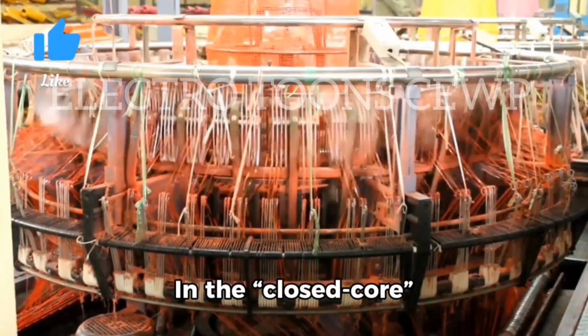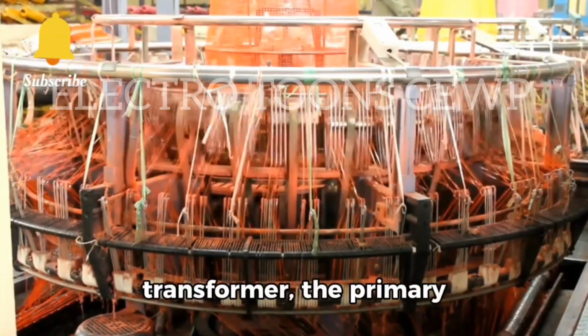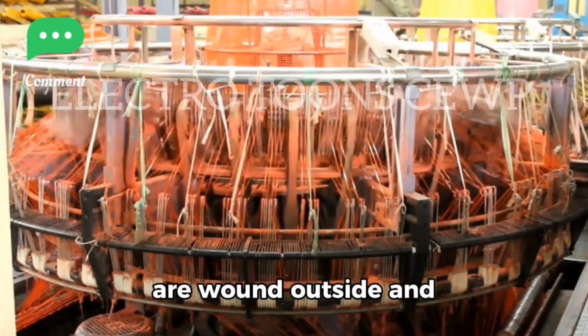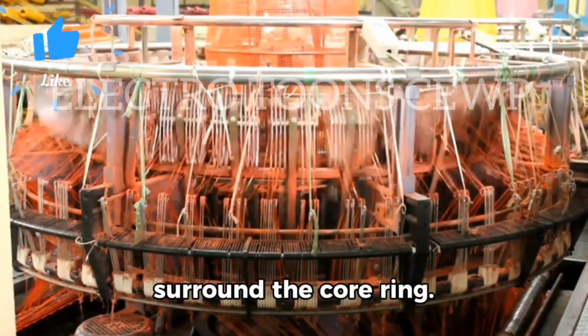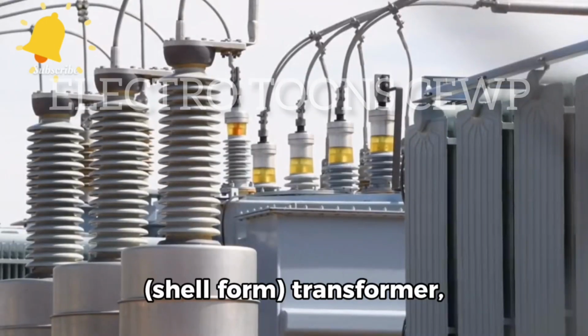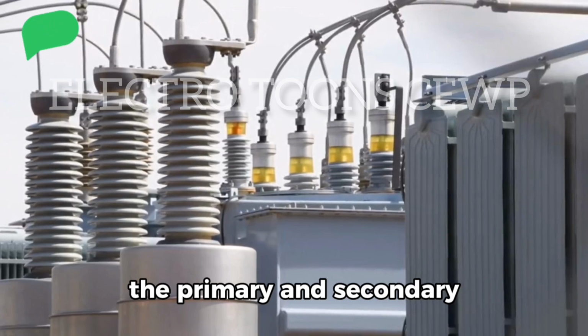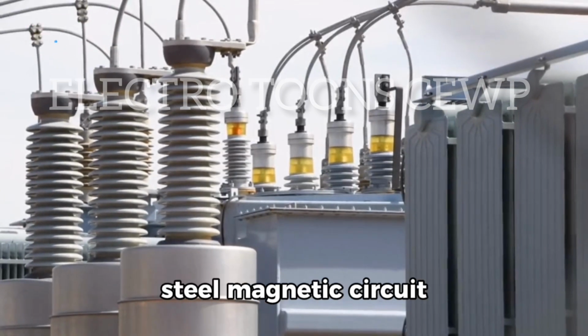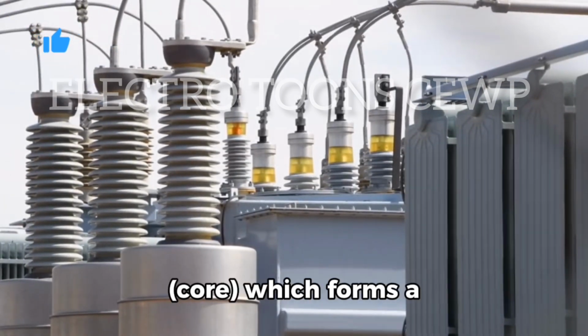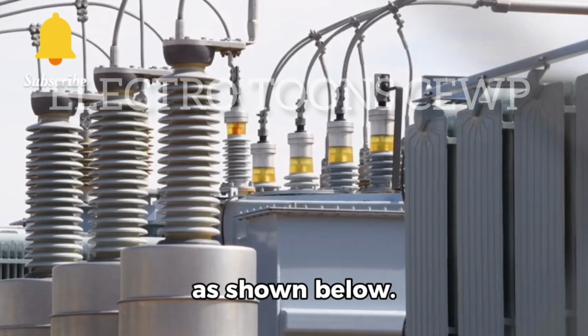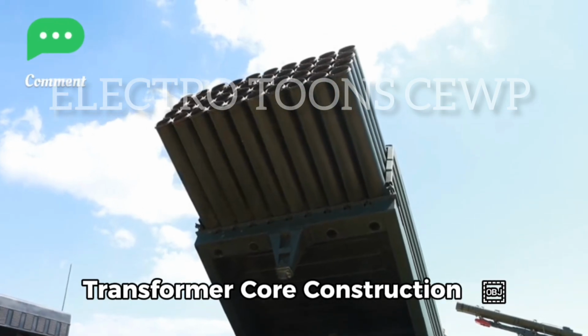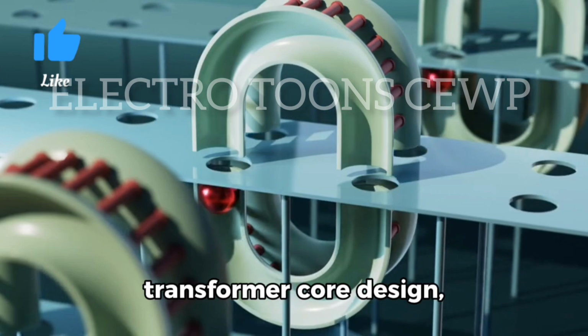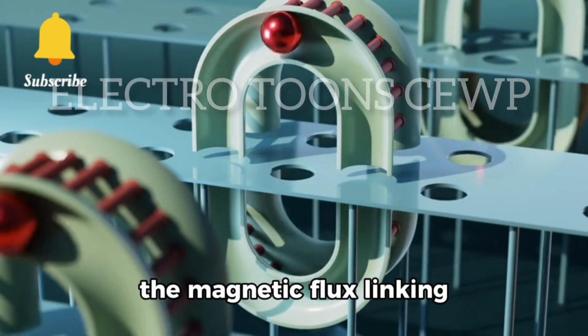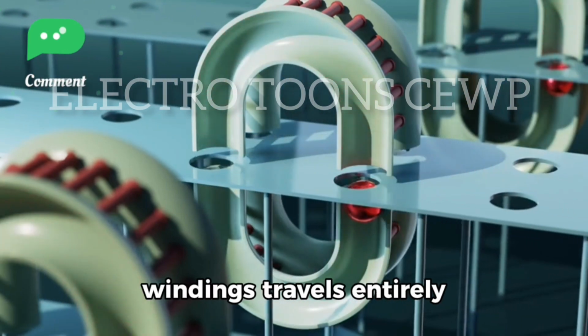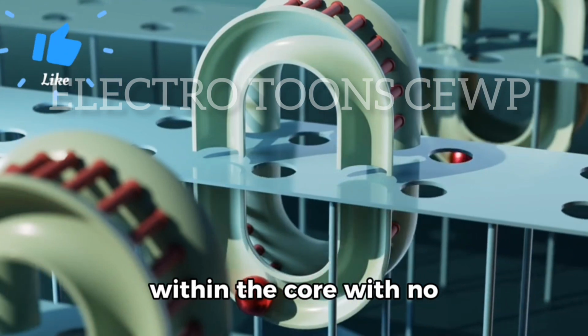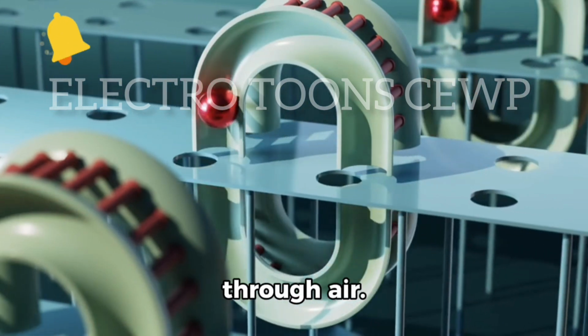In the closed-core type, or core-form transformer, the primary and secondary windings are wound outside and surround the core ring. In the shell-type, or shell-form transformer, the primary and secondary windings pass inside the steel magnetic circuit core, which forms a shell around the windings as shown below. Transformer core construction. In both types of transformer core design, the magnetic flux linking the primary and secondary windings travels entirely within the core with no loss of magnetic flux through air.